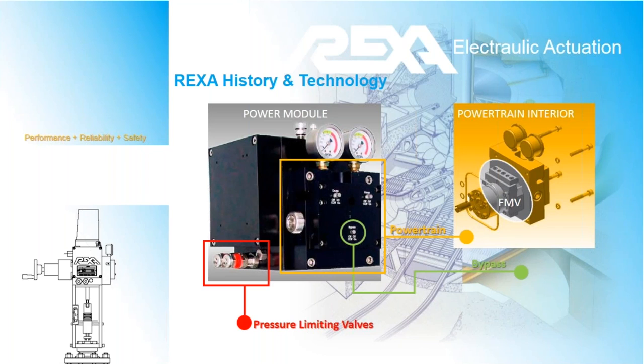The flow match valve enables the REXA hydraulic system to be a closed loop circuit, keeping contaminants out and oil volumes low. The REXA is a hydraulic technology, a motor-driven device to reach target position. Once the actuator has stroked to target position, the motor shuts off and it's hydraulically locked in place. And because of the closed loop design, there are no filters or conditioning systems in a REXA.